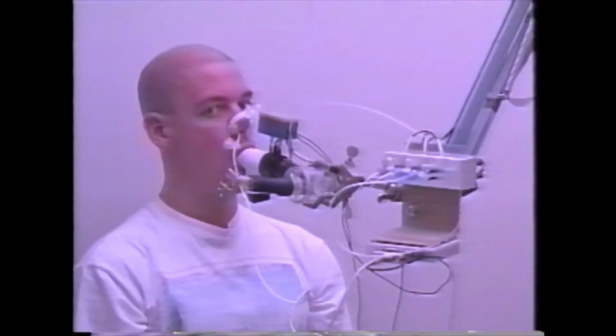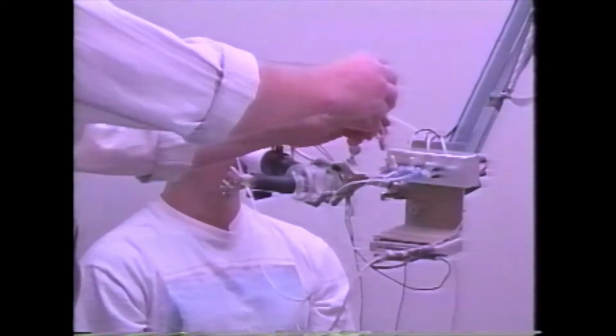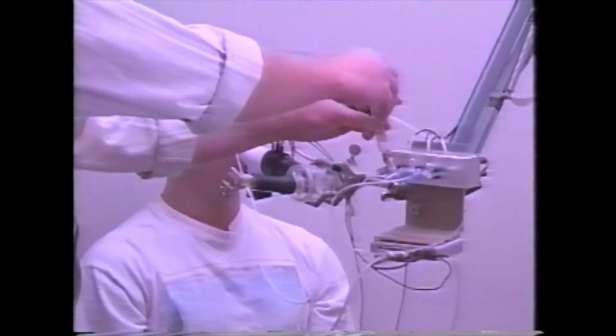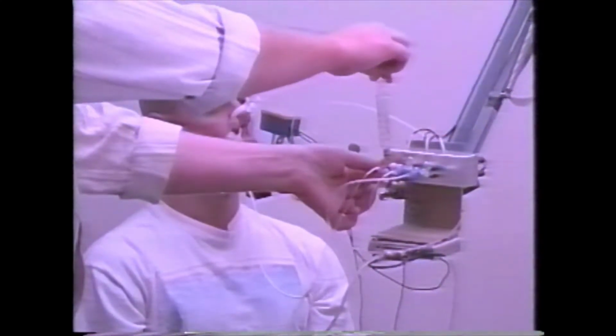The catheter is passed through the nose and positioned such that the EMG array is at the level of the esophageal hiatus, allowing for recording of crural diaphragm EMG. In order to minimize disturbances in the EMG and pressure signals, the EMG amplifiers and pressure transducers are positioned close to the patient. In order to obtain correct pressure measurements, the volume of the gastric and esophageal pressure balloons is manually adjusted with a syringe.